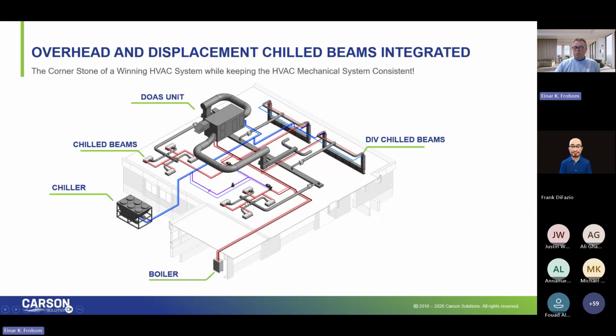So what do you do in the non-classroom spaces? Oftentimes I'm seeing overhead chill beams applied. We do manufacture those as well. It's a nice complement because it uses the same outside air, the same chilled water, the same hot water. You keep the mechanical system congruent throughout the building, same, no moving pieces and parts. Different technology. It is a mixed air system, but they're in less densely occupied spaces. It's not that IAQ isn't important, but it's important to a lesser degree than in a densely populated classroom.